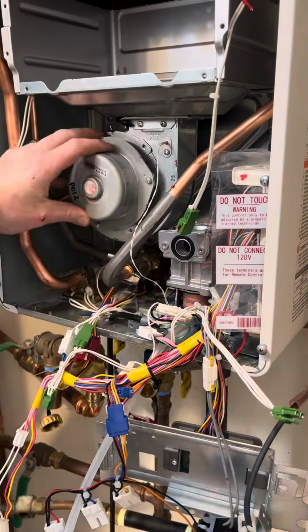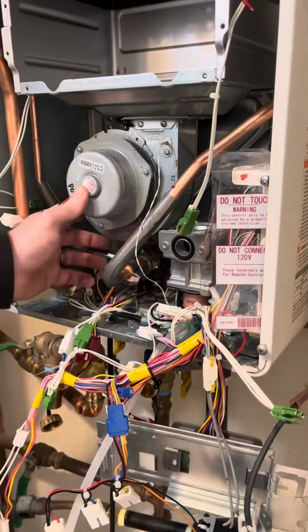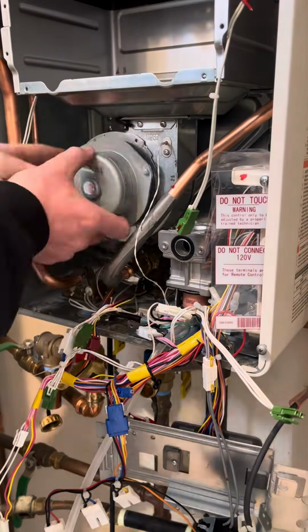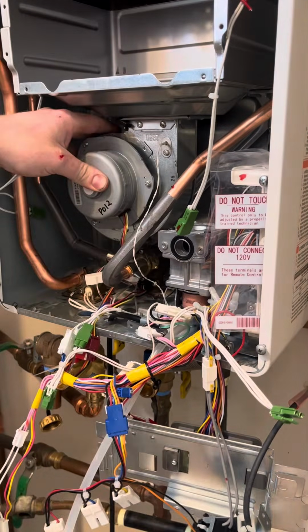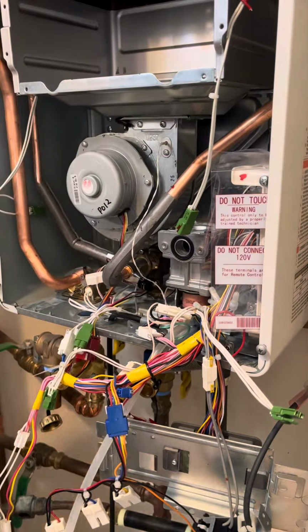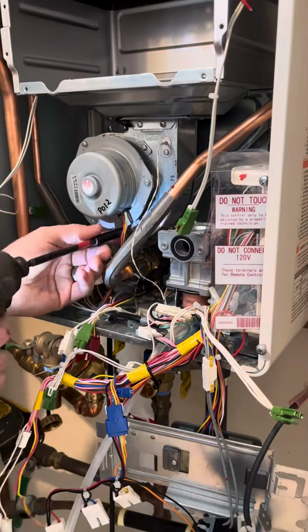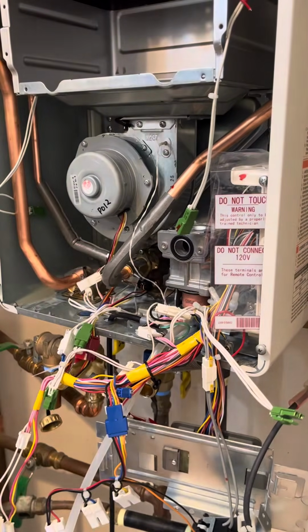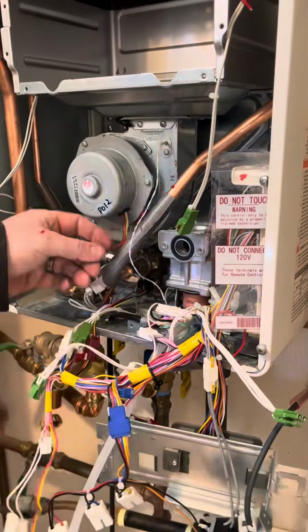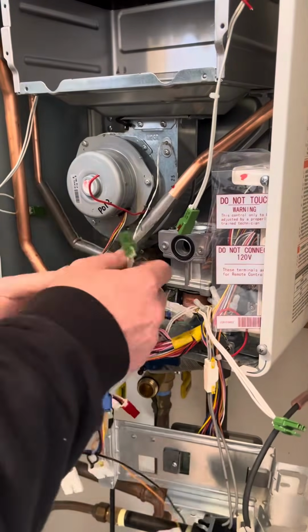This is where I put the fan motor back. Again, that probably wasn't the right thing, because once I put the burner in, I dropped the screw. You're going to see that in a minute. So again, nobody's perfect. Just remember, try to keep the fan motor out as long as possible. You're not going to be able to keep it out before you put the front plate back on, but you should keep it out at least until you get the burner in there.